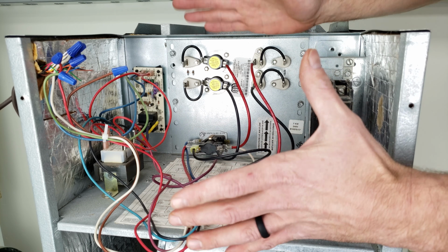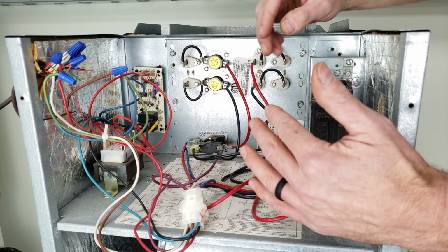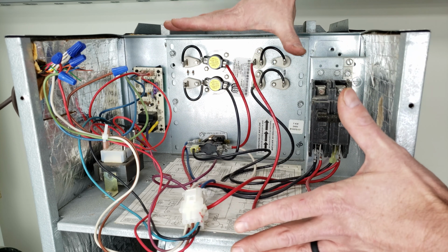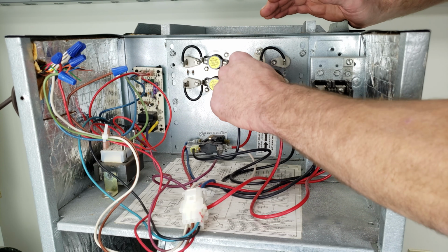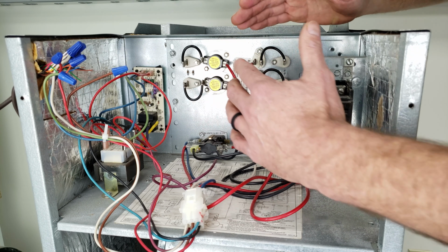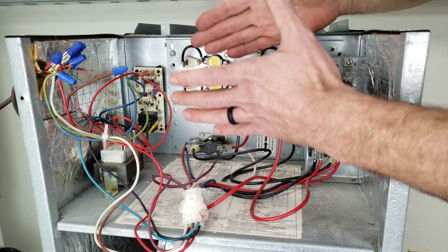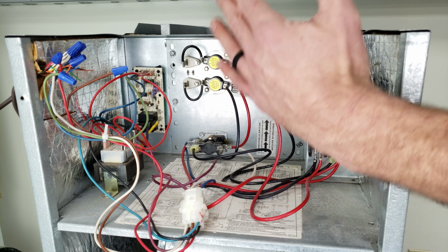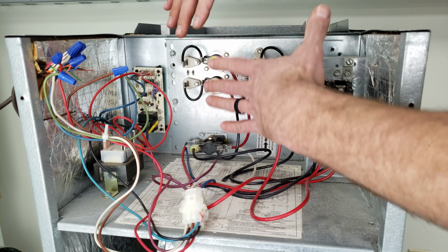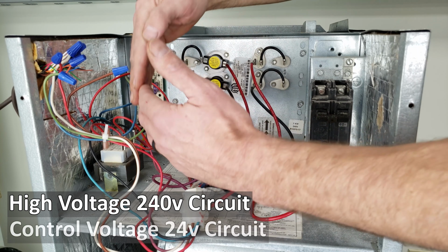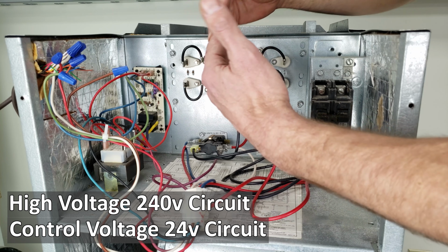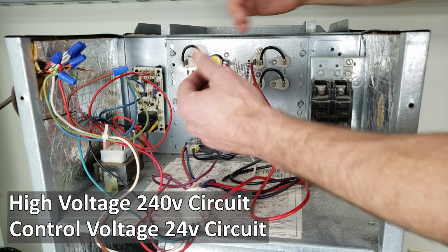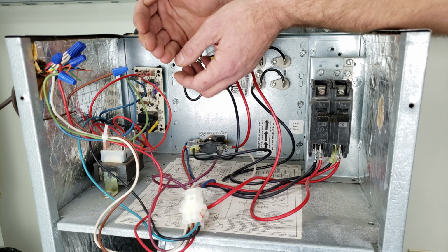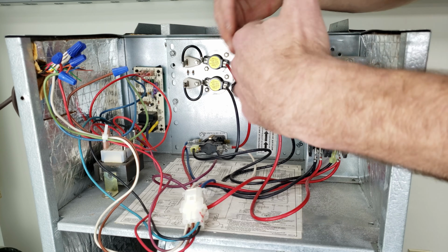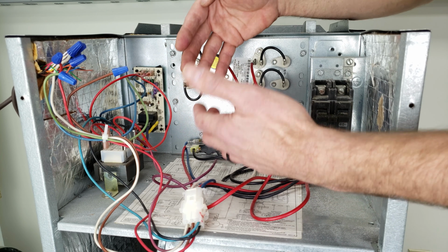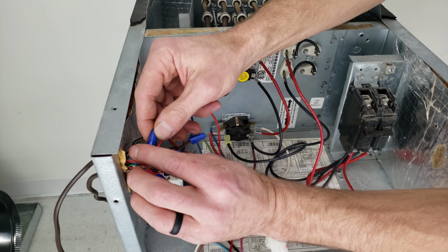When you're dealing with an intermittent problem, there are two things you want to keep in mind. One is that with the power off, you want to check all of the electrical connections. The problem is, if you don't know where to look, you basically have to divide the air handler in two: one is the high voltage loads, and the other is the control voltage. You don't know maybe where the problem lies, but you do definitely want to do something. I've seen some service techs go out to a job 3-4 times without even checking the thermostat wire connection.